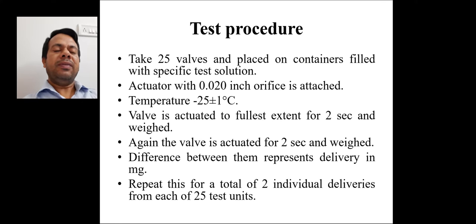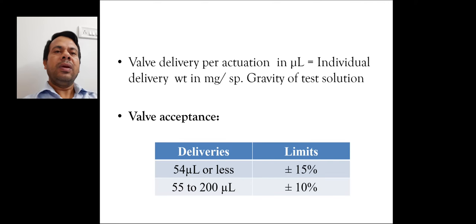So in summary, what is being done here is in first valve actuation if the weight is W1 and second actuation if the weight is W2, then the delivery will be W1 minus W2. Valve delivery per actuation in microliters equals individual delivery weight in milligrams divided by specific gravity of test solution.